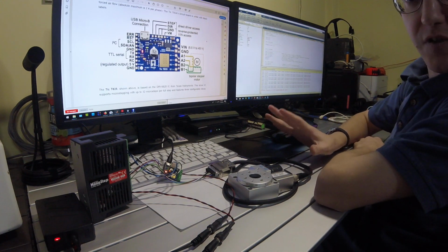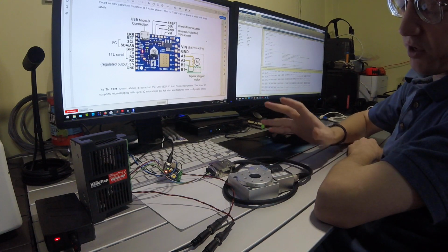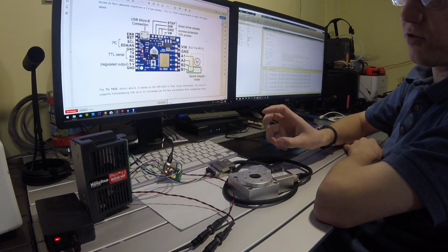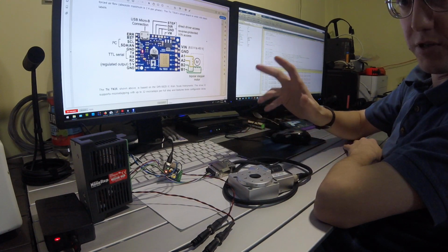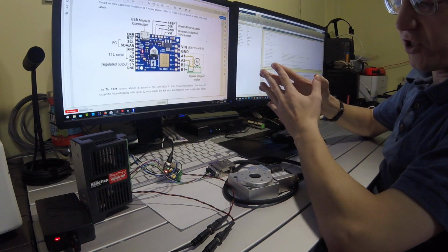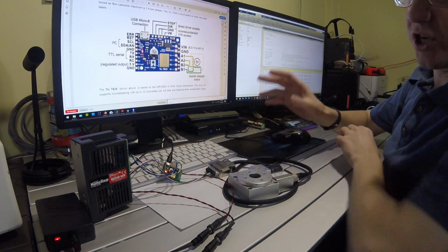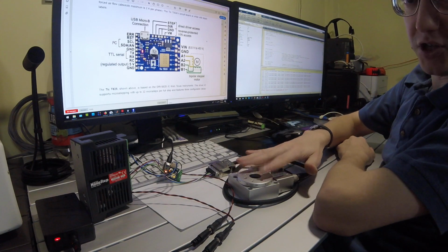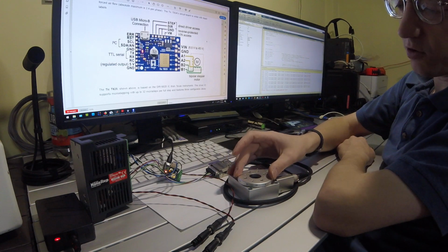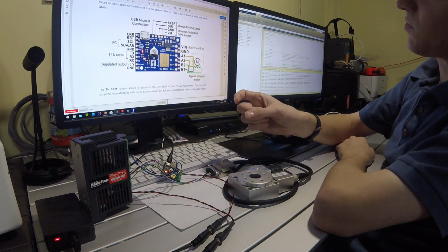So continuing on with the development of the CAT scanner conversion of the Faxitron X-ray machine, one of the things that we're going to need to do is to integrate an automated rotational stage assembly into the X-ray cabinet in order to rotate the object which is being scanned. There's several possibilities to do this. One is with a stepper motor with a right angle gearbox. The other is with just the stepper motor itself. The right angle gearbox is obviously going to have a lot more physical capacity to scan larger objects and also potentially a finer resolution, whereas the single stepper itself will be smaller.